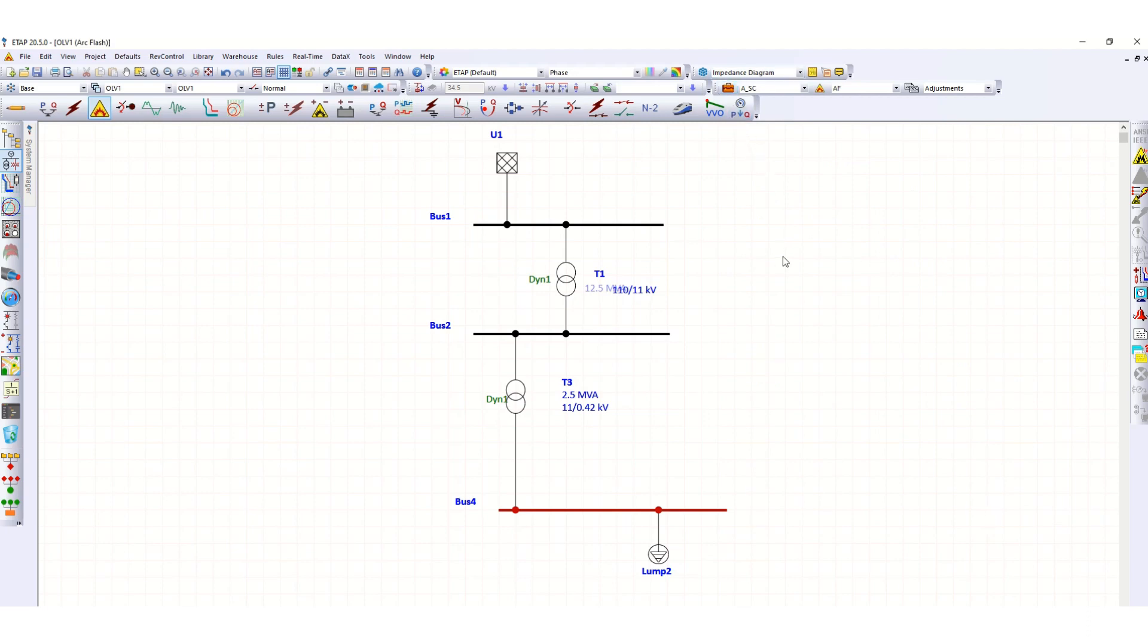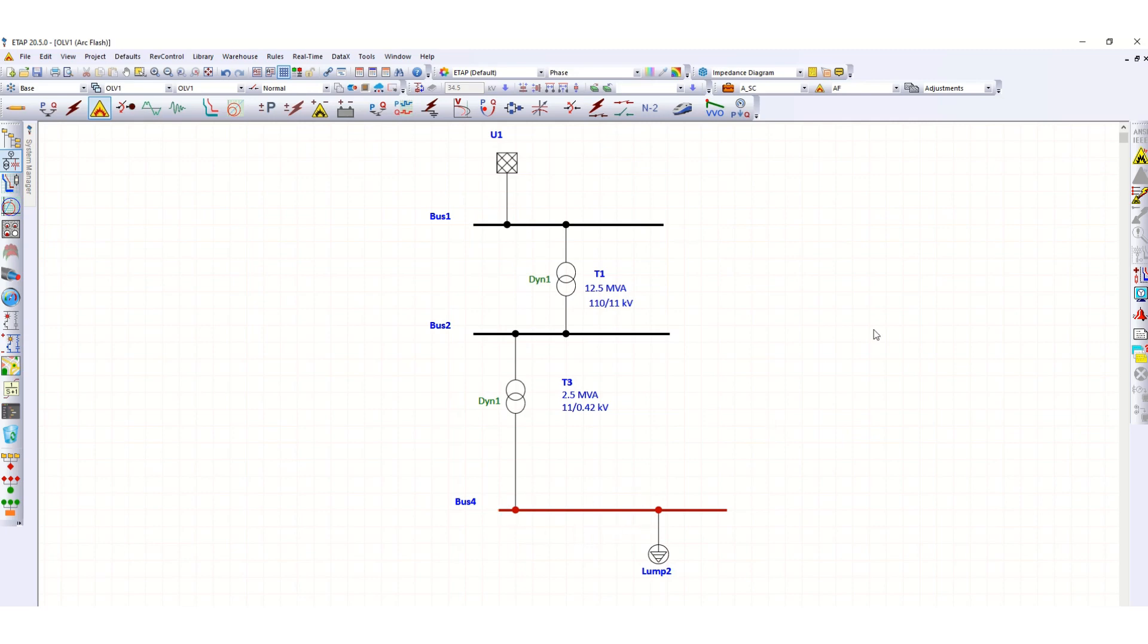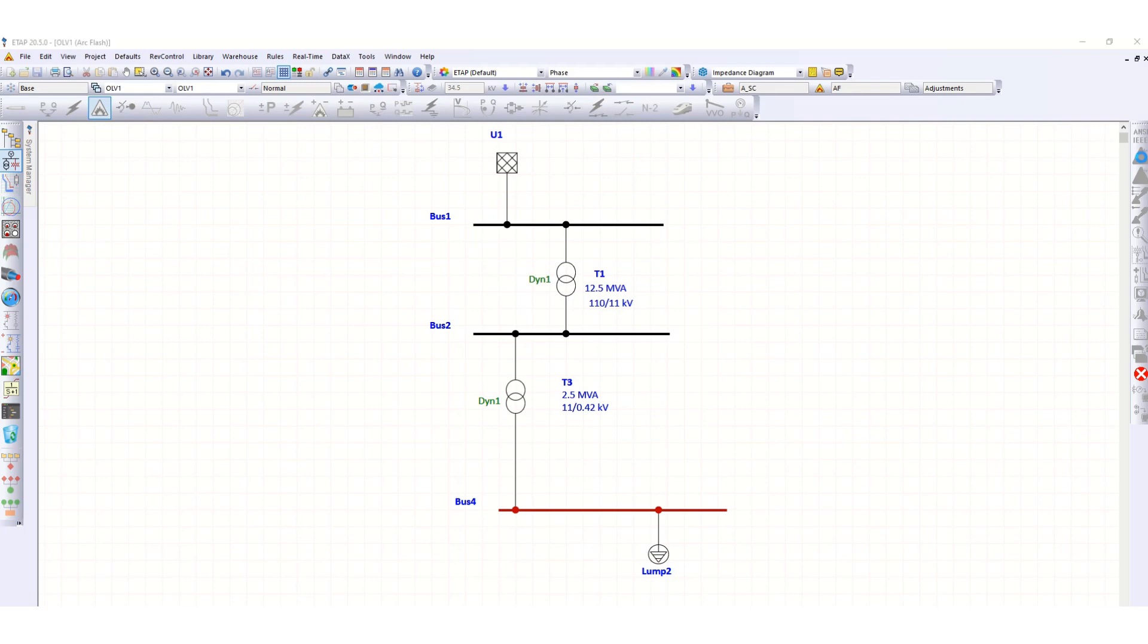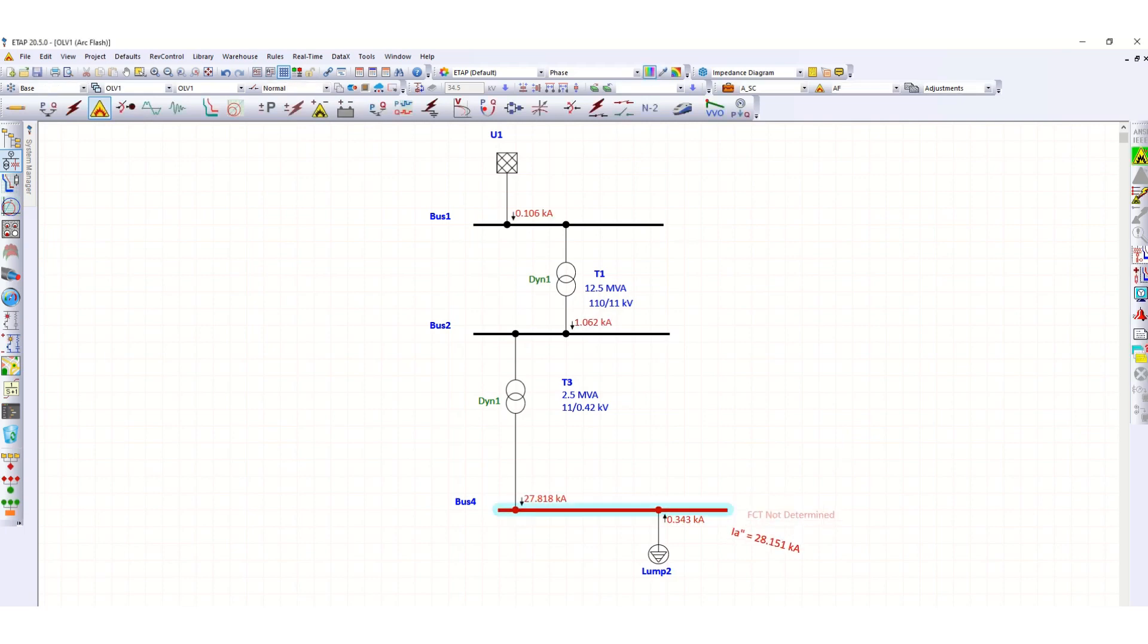Now we are going to check the Arc Flash analysis for this bus 4. Let's run Arc Flash as per IEEE 1584. Here you can see FCT not determined, there is an error. Why is this showing? Because...